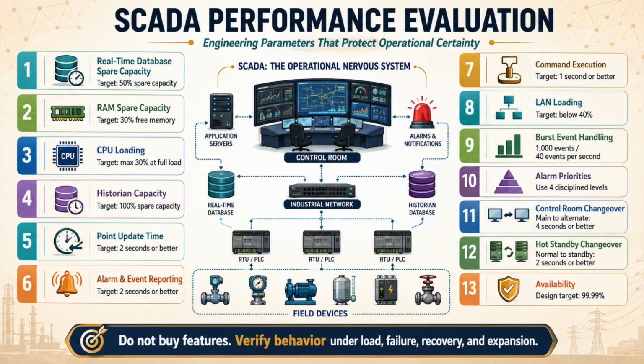So testing must generate the expected event volume, confirm storage growth, verify retrieval speed, prove archive behavior, and validate backup and restore performance. The 20th engineering parameter is overall system availability, because 99.9% availability is not achieved by writing redundant server in a specification. Availability is an end-to-end property involving servers, storage, switches, firewalls, power supplies, time synchronization, virtualization hosts, clients, historians, backups, cybersecurity tools, patching strategy, spare parts, support contracts, monitoring, and operator procedures. Redundancy is a feature, but availability is the complete outcome.